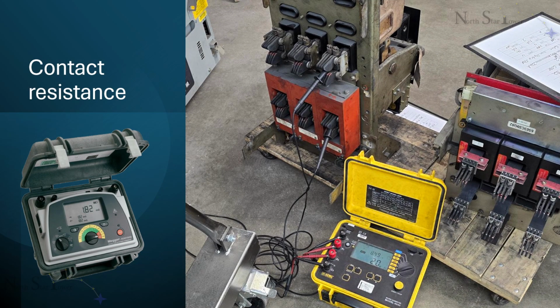Once we've confirmed the breaker trips correctly, we assess how well it conducts electricity through contact resistance testing. Inside every breaker are contact points, often made of copper, silver, or tungsten, that carry the system's current. Over time, the contacts can degrade from corrosion, arcing, or loosened connections, increasing resistance at the junction. Excess resistance causes localized heating, electrical stress, and, in extreme cases, arc flash or fire, but these issues are invisible without testing. Using a ductor, a low-resistance ohm meter, we inject high current through the closed contacts and measure the voltage drop to calculate resistance in microohms.